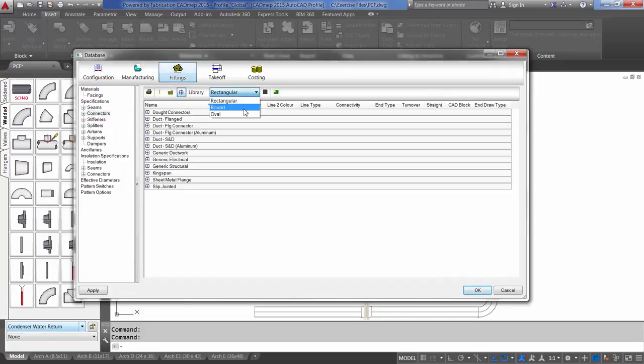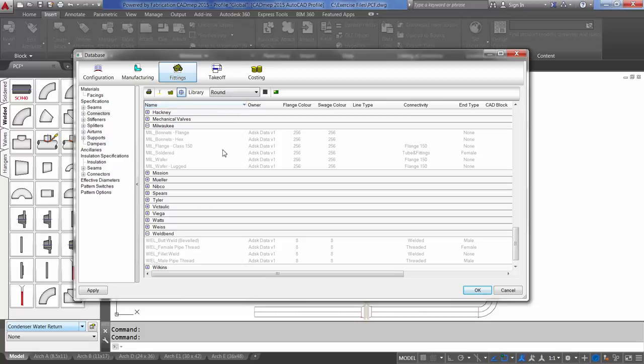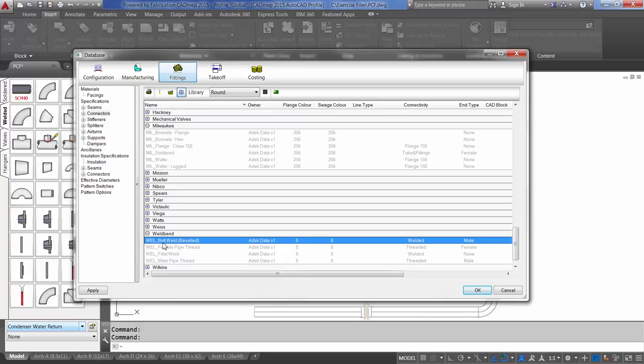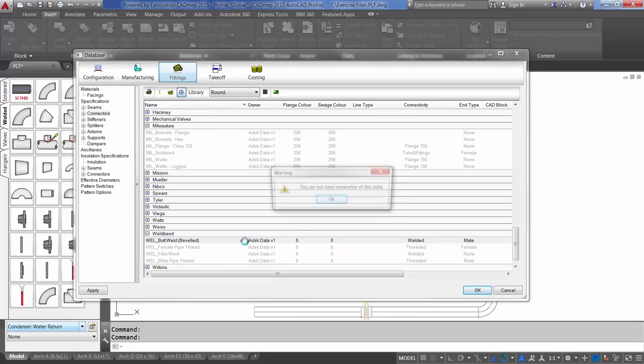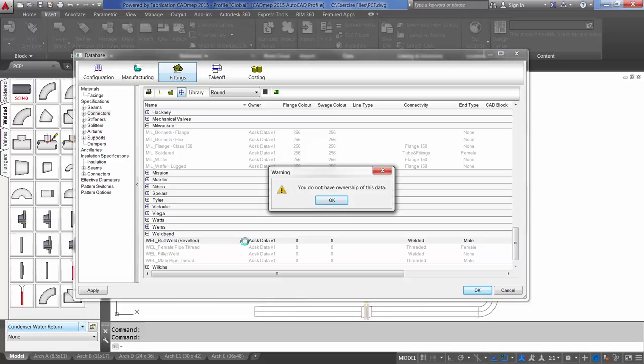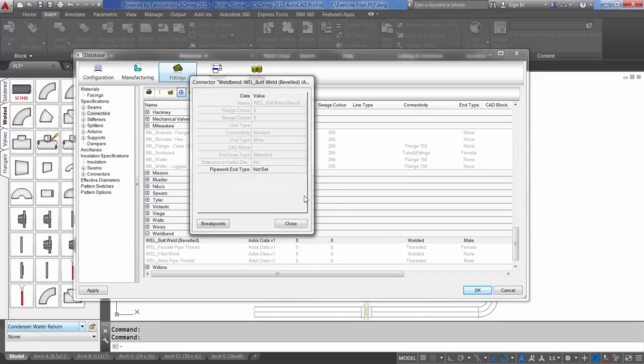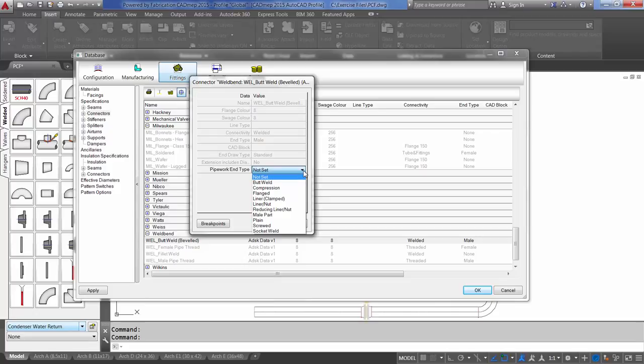Select Round. Let's take a look at our Weld-Bend Butt-Weld Beveled Connector. Make sure that you have selected the drawing section of the database and double-click to open up the properties. You'll get a warning that says you do not have ownership of this data. Select OK. We do have the ability to set the pipework end type. This is what we need to set on all of our connectors for the file so that it has the correct information when bringing it over to Plant 3D.